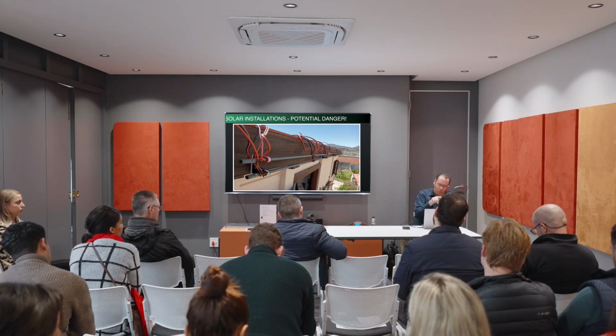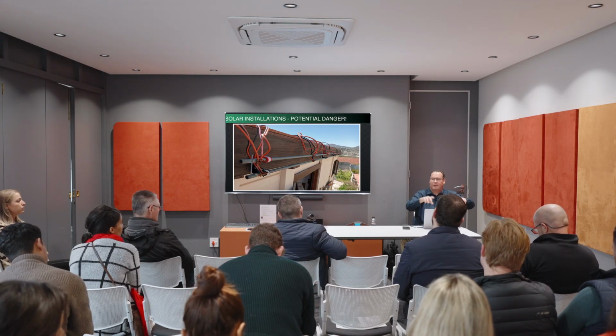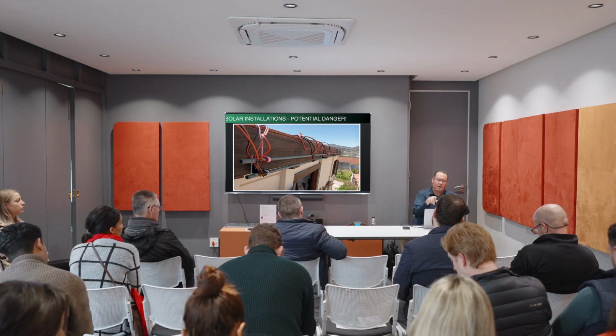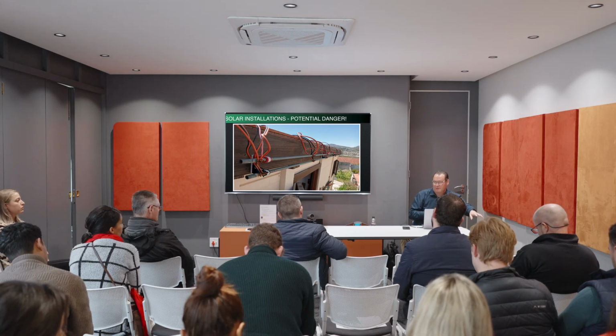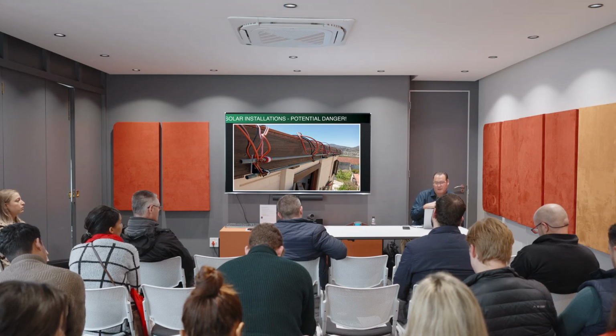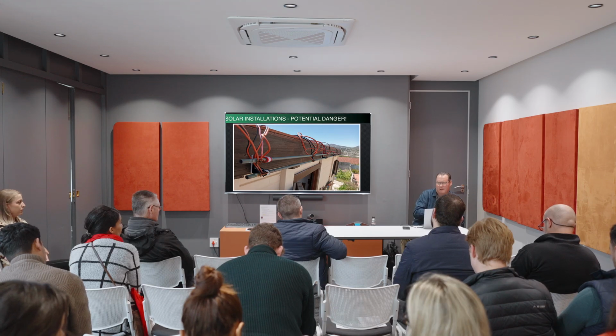Each set of panels is called a string, and the cables that come down are called a string. You don't want 2 strings in the same conduit because of this arcing problem. The right way to do it, and I'll get to that in a minute, is metal conduit, but lots of people are using plastic, and it is still allowed.